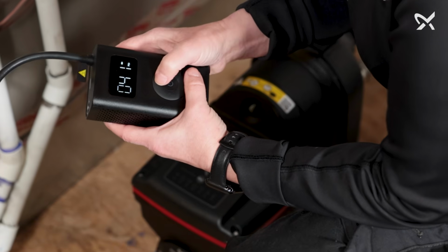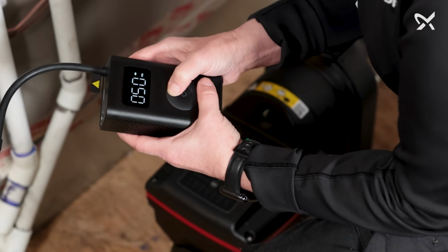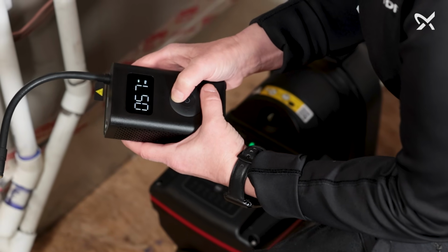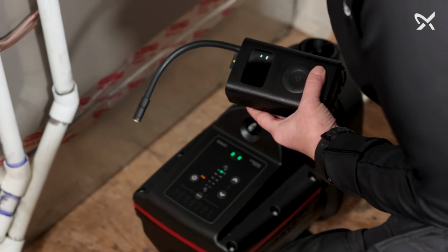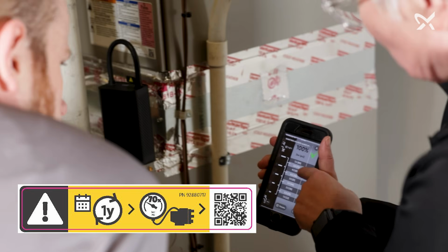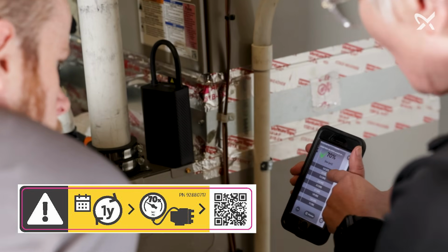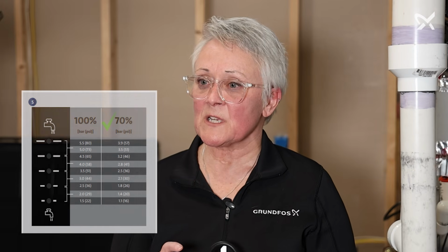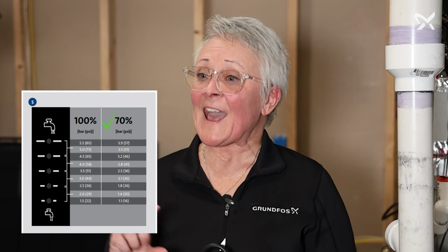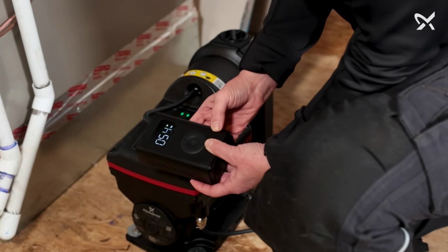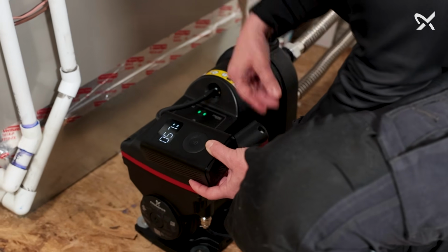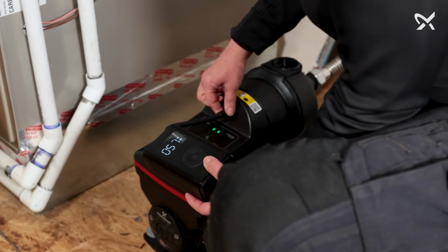Now we've stopped the pump and we're going to set the internal pressure of the diaphragm tank. Because this is a VFD drive, we need to set that tank at 70% of our discharge pressure. Okay? On the pump, there is a QR code. If you scan that code, it will lead you directly to the quick sizing guide that will show you all of the PSI increments on the pump and the corresponding internal pressure for the diaphragm tank. You'll need a small compressor and the ability to put that precharge into the tank.